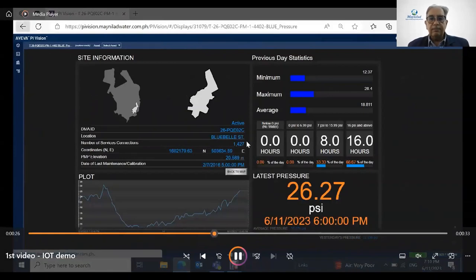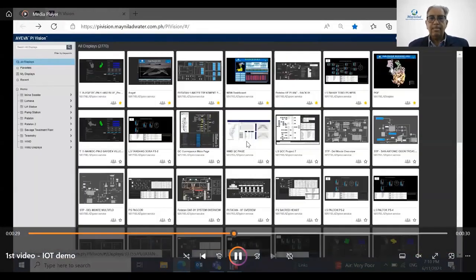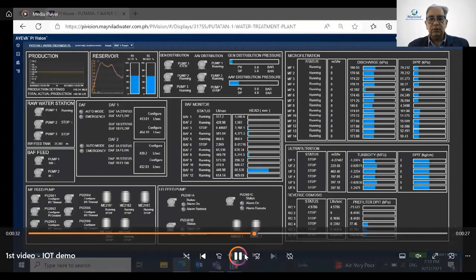Another example: this is on a plant, and this is almost real-time information. You can see the status of several pumps, critical equipment, whether it's running or stopped. These are filters here—we can see the pressure on the filter, and also the differential pressure. Differential pressure on a filter typically tells you whether it needs cleaning because it's clogged—the higher the differential. We can see different pressures on different parts of the plant and the level of the reservoir.